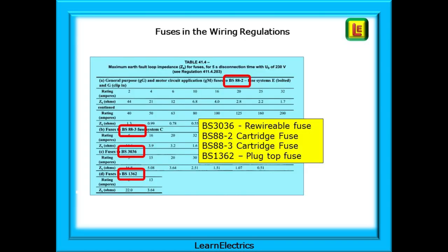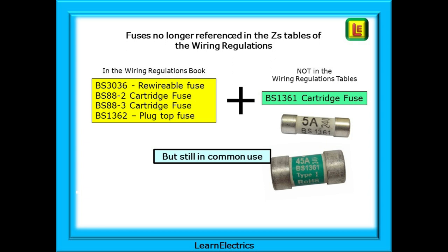The wiring regulations give ZS data for a limited range of fuses on table 41.4. We have BS 3036 rewireable fuses, BS 88-2 and BS 88-3 cartridge fuses, and the BS 1362 plug top fuse. BS 1361 cartridge fuses no longer appear in the tables, although they are still a very popular fuse especially in older commercial and industrial installations. Just because it's not in the regs book doesn't mean that none exist.